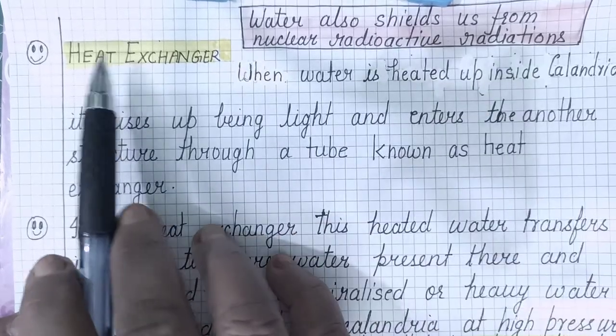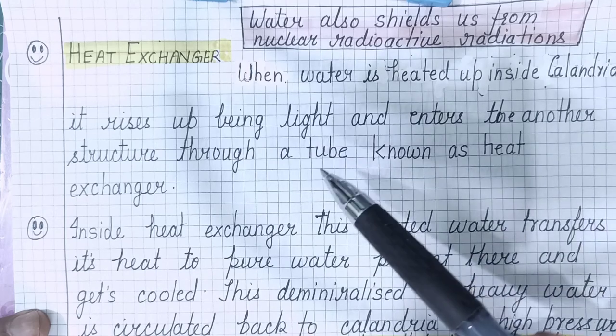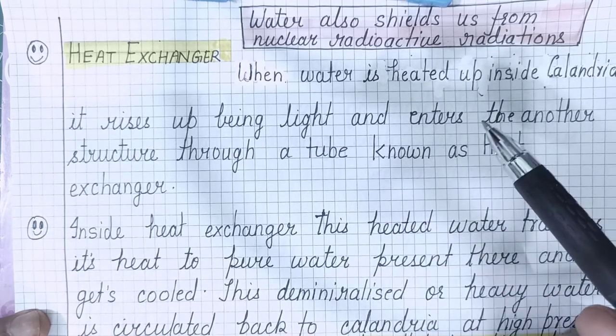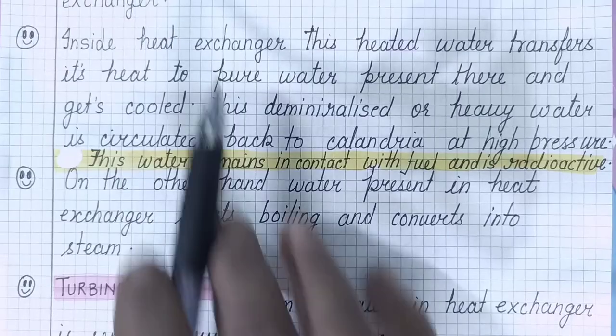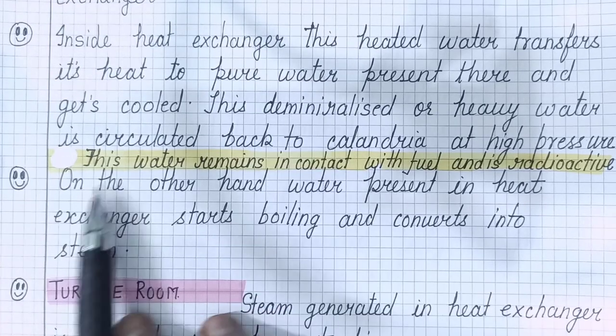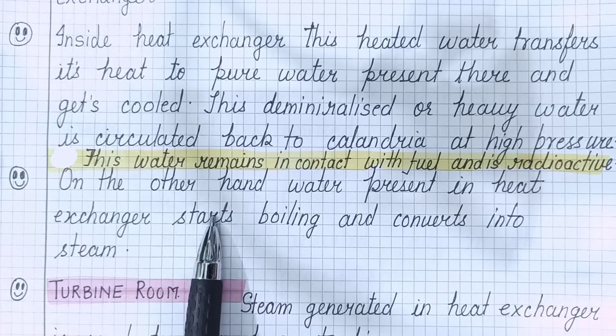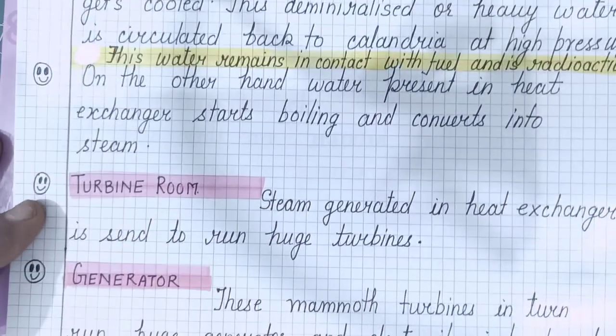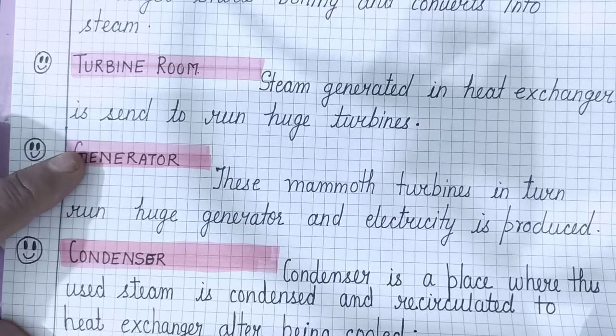The hot water from the nuclear reactor core calandria moves to the heat exchanger. In the heat exchanger, it comes in contact with cool water, gives its heat to that cool water, and is then pumped back into the calandria at high pressure. The cool water in the heat exchanger, having absorbed heat from the coolant, starts converting into steam and moves to the turbine room, where it rotates the turbine and runs the generator to produce electric energy.